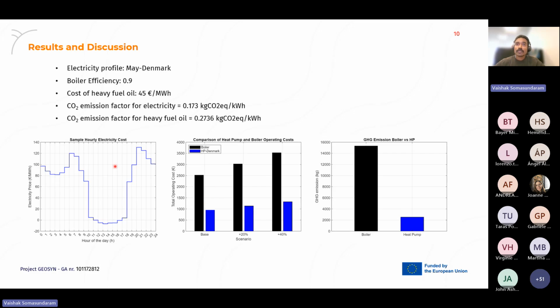When we are comparing the operating cost of the heat pump with that of a boiler, it can be observed for the baseline scenario that we are able to obtain approximately 60% reduction in the operating cost. Now, for the considered electricity profile, even if we increase the electricity cost by 20 or 40%, the operating cost of the heat pump will still be less than the baseline operating cost of the boiler. It is very important to note here that currently we have considered a Denmark scenario, which relies mostly on renewable energy sources. However, for countries which rely on natural gas or thermal power plants, the scenario will be different. For example, for countries like Italy, the operating cost of the heat pump will be higher than the one we are having for Denmark.